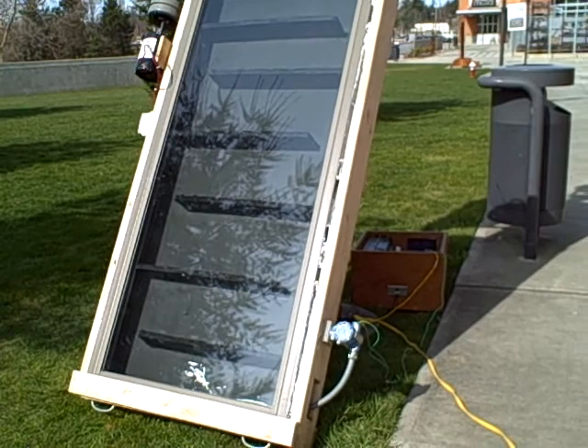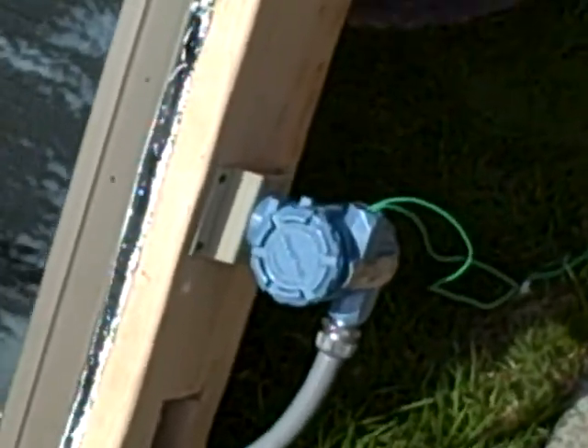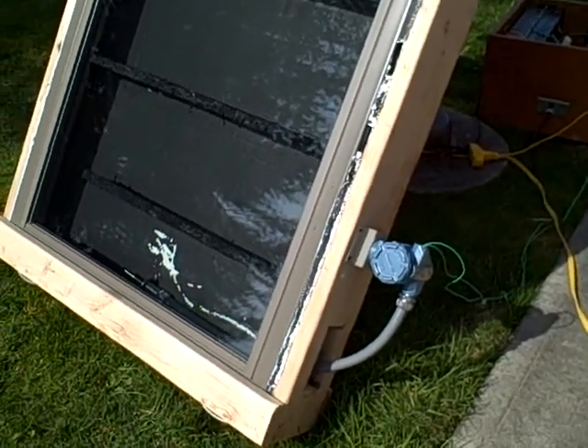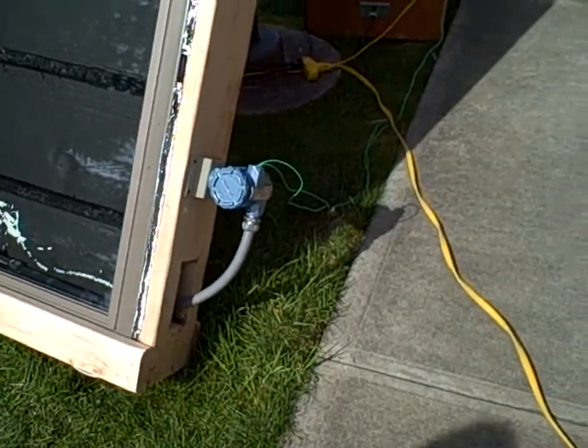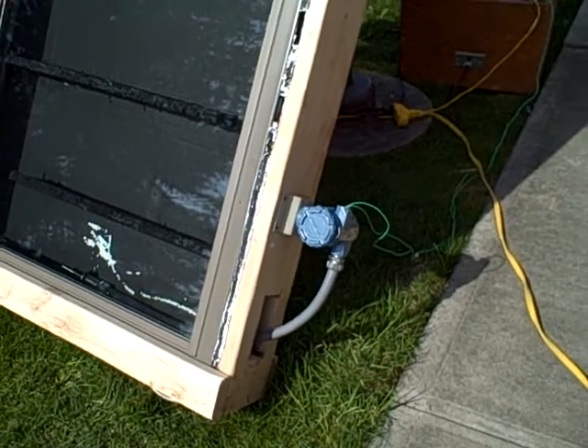That little blue thing right there is a temperature transmitter. This temperature transmitter has a sensing element. The sensing element is an RTD, specifically a four-wire RTD. Basically what this is doing is sensing the temperature of our process variable, which is actually just the temperature of the air within our solar collector. This transmitter outputs a 4 to 20 milliamp current based on the temperature of the air that it's sensing from the sensing element in the solar collector.